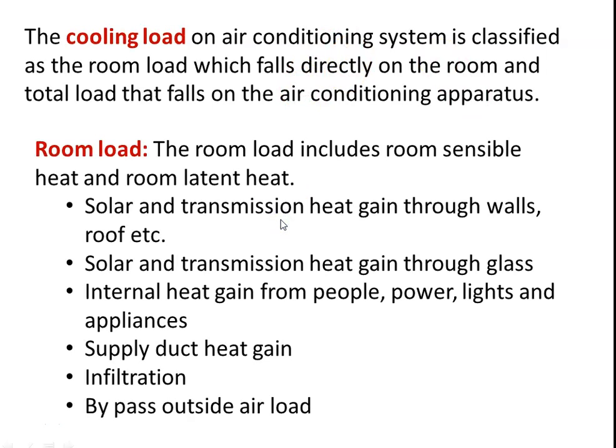What are all the room loads? Room load includes the room sensible heat and room latent heat, then the solar and transmission heat gain through the wall and the roof. So what are the components? The solar radiation falling on the wall, the solar radiation falling on the roof, and the amount of heat transmitted through the side wall and the roof into the air conditioned room. That is the cooling load. Then the solar and transmission heat gain through the glass, the window glass, or there may be a glass door. Solar heat is transmitted through the glass, and that also adds to the heat load.